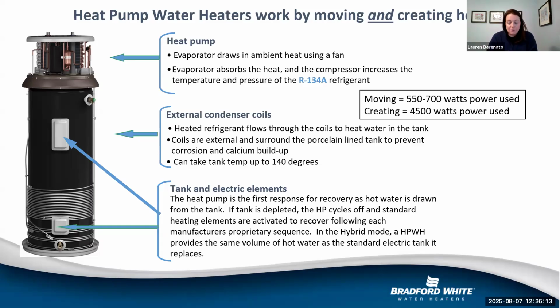But so, Legionella prevention. Most water heaters in a commercial setting are stored at 140 degrees Fahrenheit. If you're going to do a thermal disinfection, you will run it up higher. Typically you'll either use your main heater and have that go all the way up, or you will have some type of booster heater that will also have it go up to 160 degrees Fahrenheit.